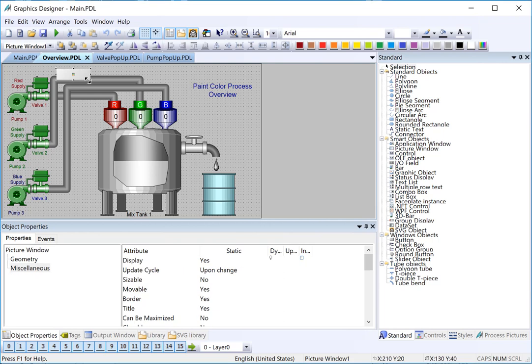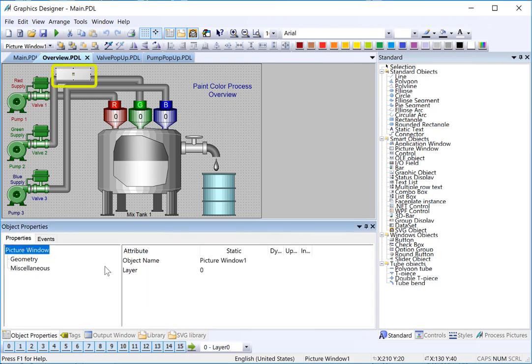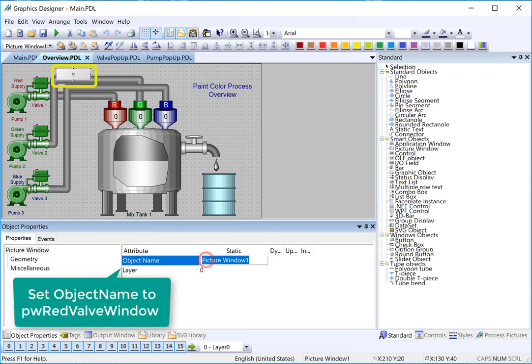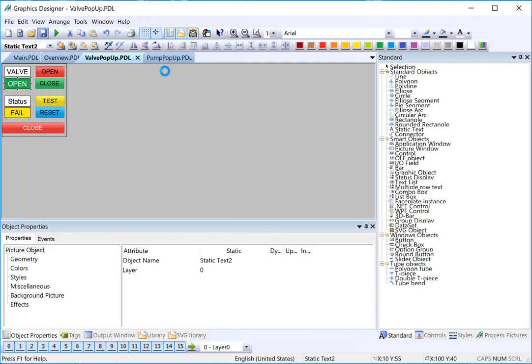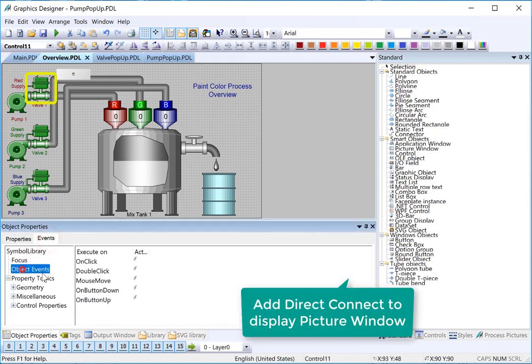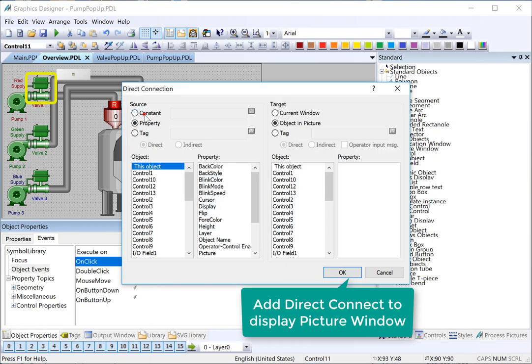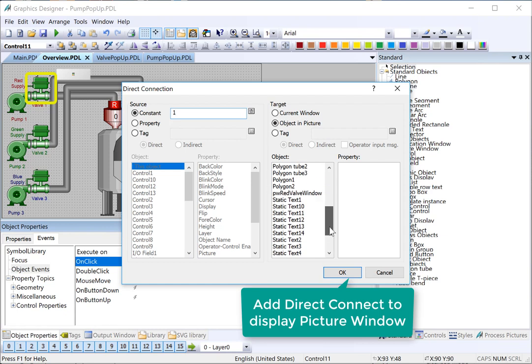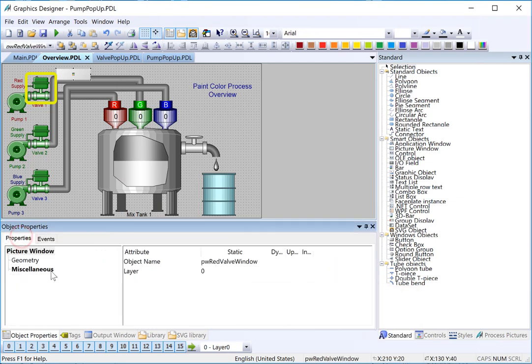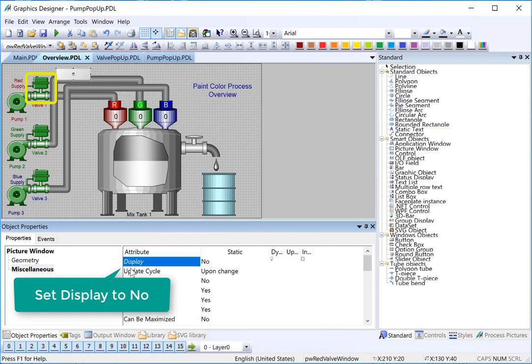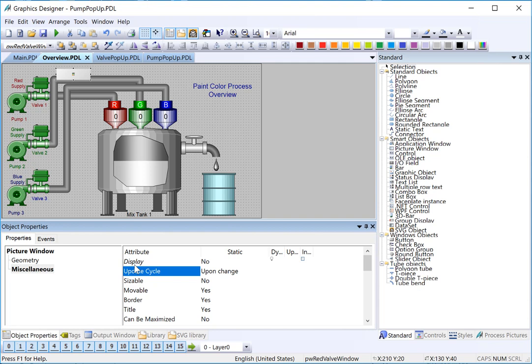Next, we're going to duplicate that and make it so that when you click on the valve we can call that pop-up, because once you close it there's no way to get it back. We'll go back to our overview screen and look at the name of this picture window — it's picture window one. We're going to change that because we're going to create six of these, one for each pump and valve. I will call this PW red valve window. I also noticed that we couldn't read the open and close labels very well, so we're going to change the font to white. I'll go back to my valve pop-up and make it white, hit save, and do the same thing on the pump. On the valve, we're going to use a direct connect to turn on the display of that picture window — we'll put a constant one into the display property. Then by default we'll turn off the display so it doesn't come up automatically. Notice that display is italicized because the direct connect is now controlling it.